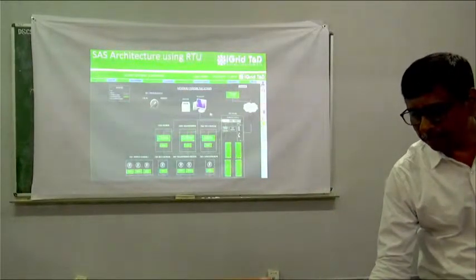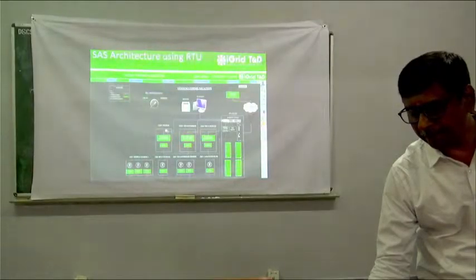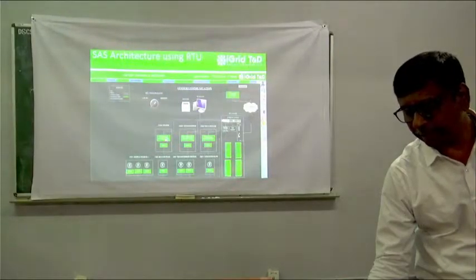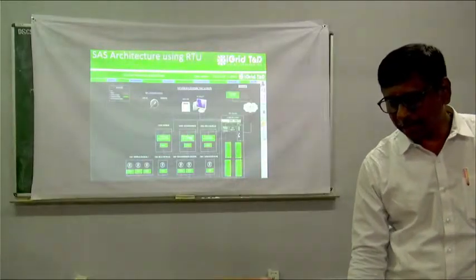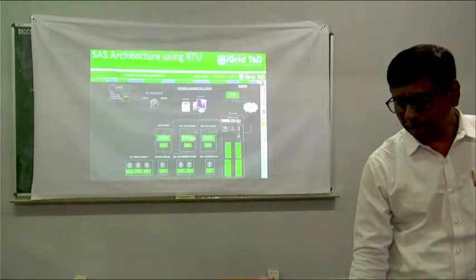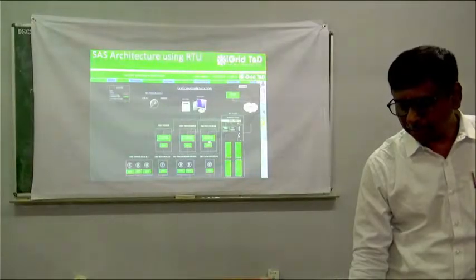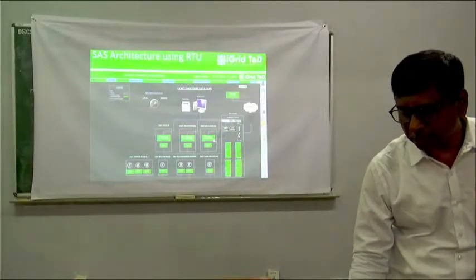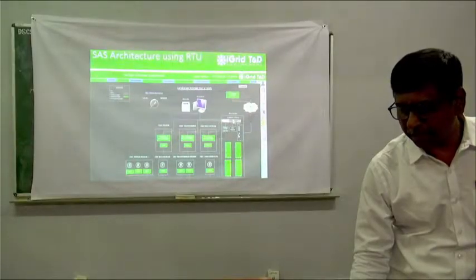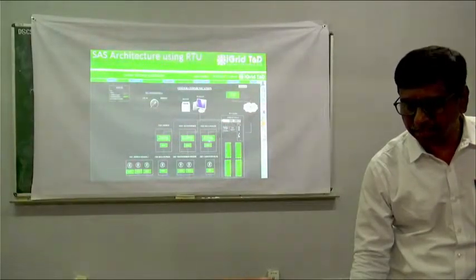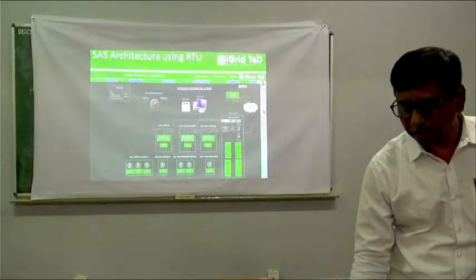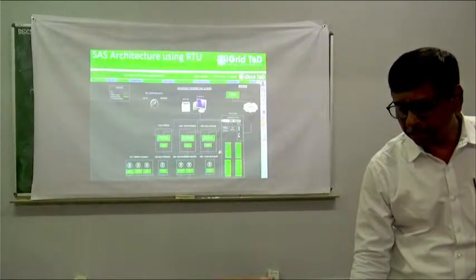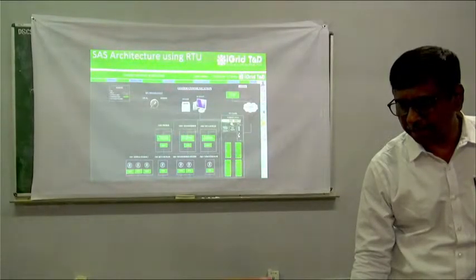Okay. Now, if you observe the architecture here, we have a 132 kV feeder. The 132 kV feeder has a distance protection relay, and the 132 kV transformer has a differential protection relay. Okay, and we have a 132 kV bus coupler, which is again a distance protection relay. All these relays, if you observe, are connected to an Ethernet switch because they communicate on IEC 61850. Every feeder or panel has a multifunction meter, daisy chained, and these meters communicate data on Modbus, which in turn is connected to a Modbus TCP/IP converter and again connected to the switch.